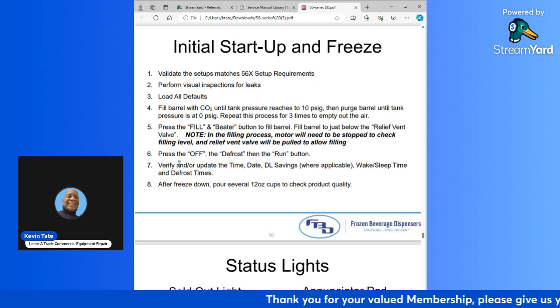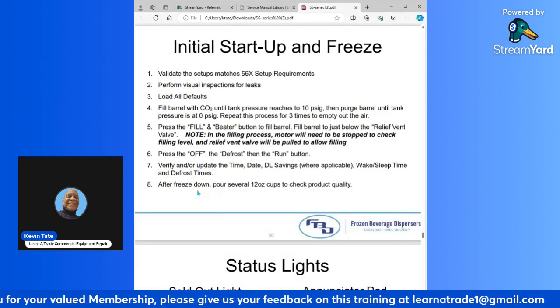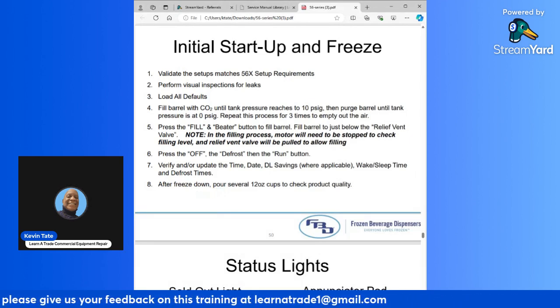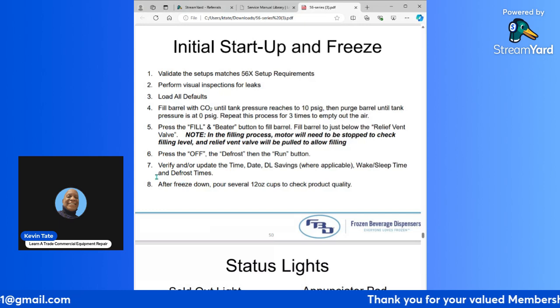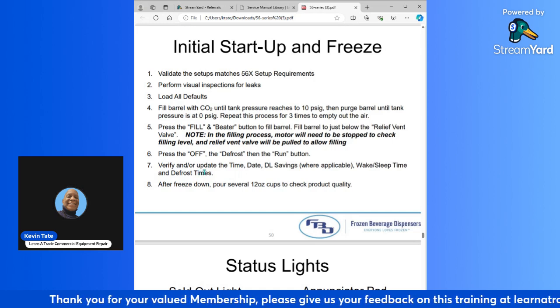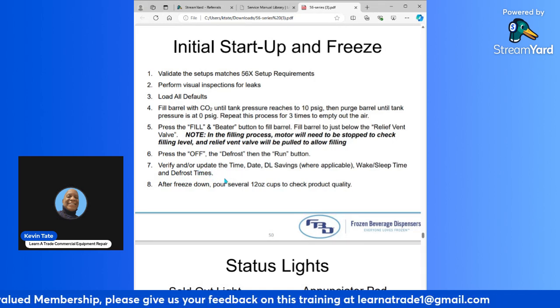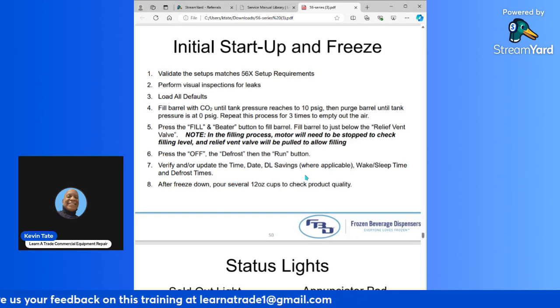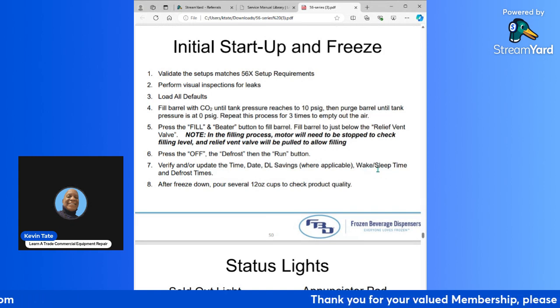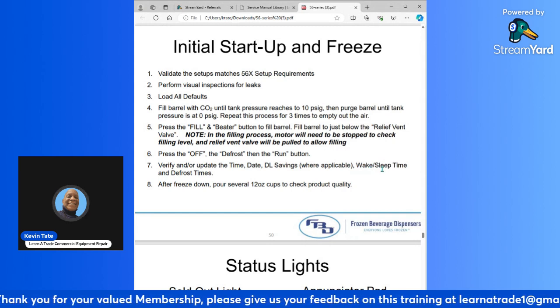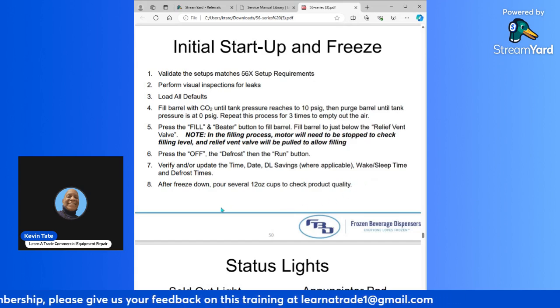Then the next step is press the off, the defrost, and then the run button. Verify and or update the time, date, daylight savings time where applicable, wake up sleep time, and defrost time. So you're just going through the readouts to verify. You're going through the service menu to verify your date and your time, make sure everything's correct. Make sure that your wake up and sleep is not set for certain times or anything like that. If it's a 24-hour location, if it's a private location and they have wake up times, you want to make sure you have the correct time set.